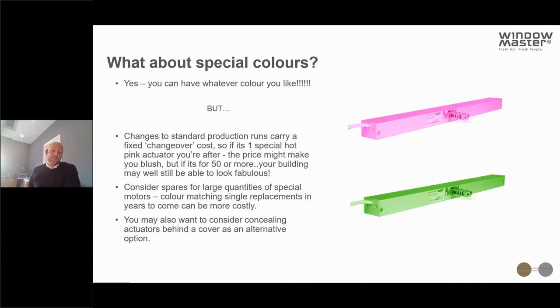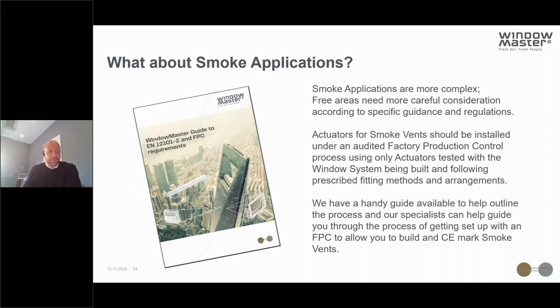Concealing actuators behind a cover profile is often a very cost-effective alternative to colour matching. For smoke applications, free areas need more careful consideration according to specific guidance and regulations. Actuators used in smoke applications must be installed under an audited factory production control process, using only actuators and components that have been jointly tested following prescribed fitting methods. We have a handy guide on our website and a specialist in-house who can guide you through setting up an FPC to allow you to build and CE mark smoke vents.